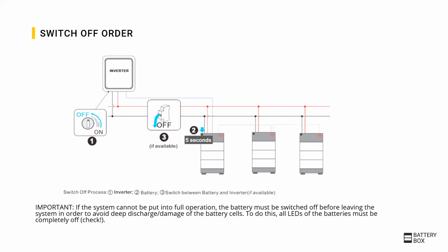If there are problems with the system and it cannot be put into full operation, it is very important to always switch off the battery completely before leaving the system. Here, all LEDs should be completely off. Also, the system should then be put into operation within a few days, or the service should be contacted. Please note that improper handling can damage the battery.